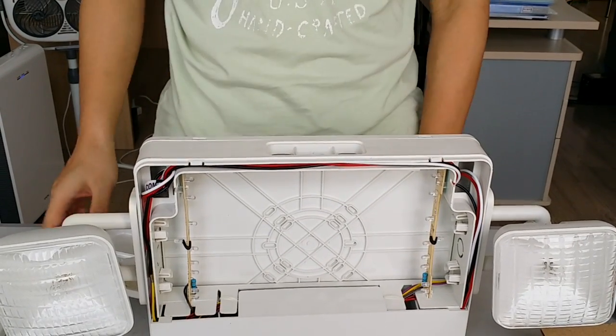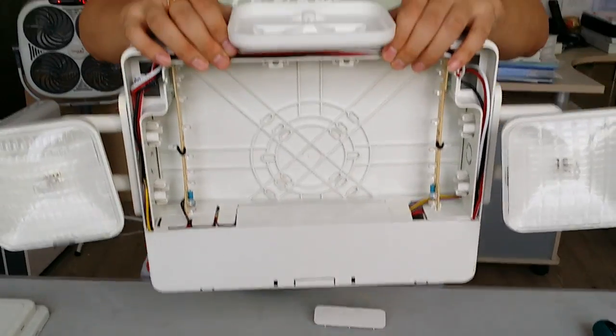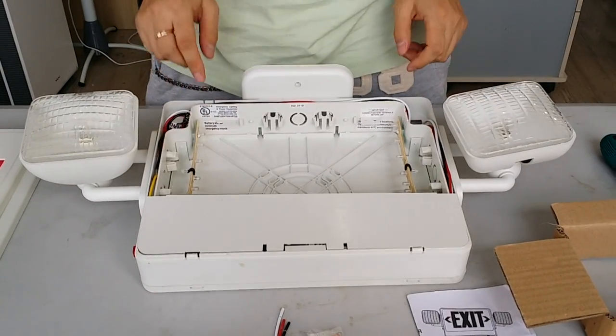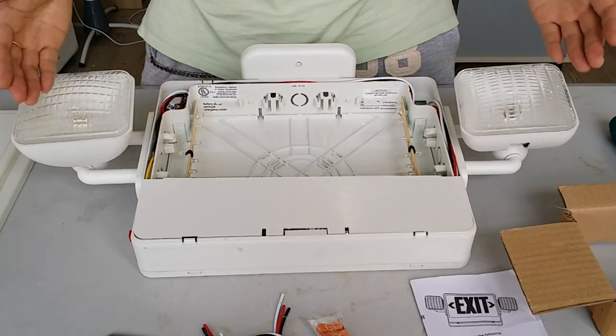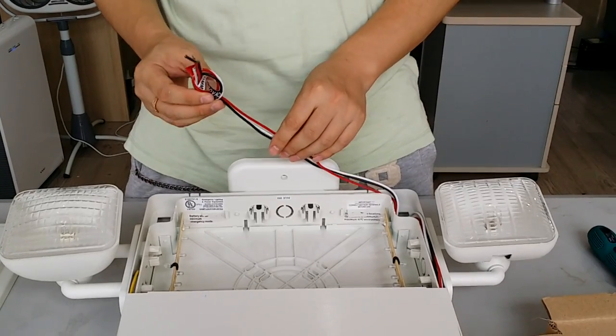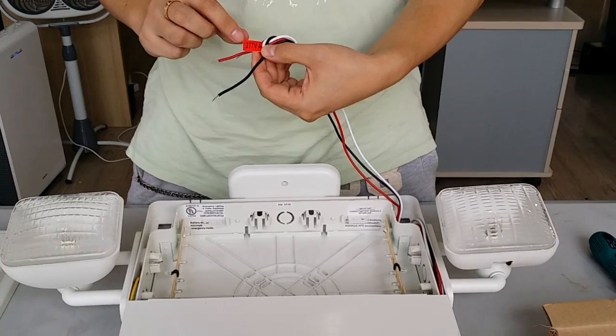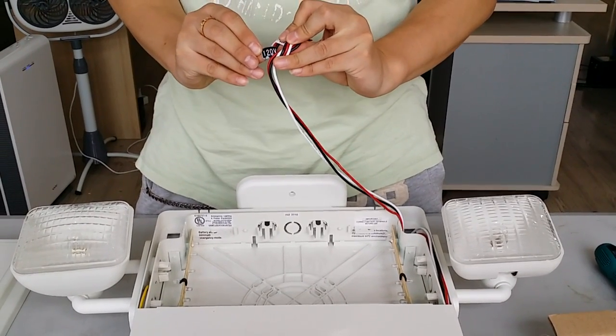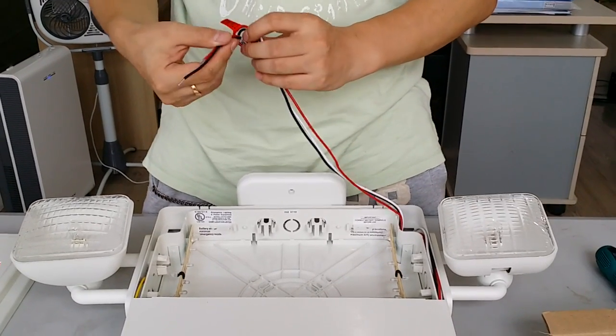The instruction manual is included. After removing the part, you can fix it on top. The panel uses LED lights. Here is the incandescent bulb. The light supports dual voltage — one option is 277V and the other is 120V. Follow the instruction to choose the right voltage.